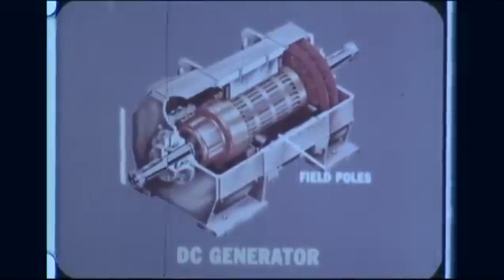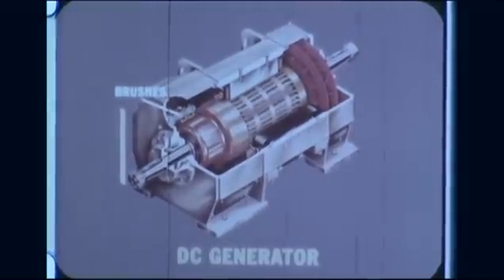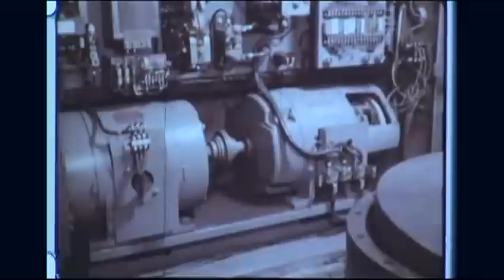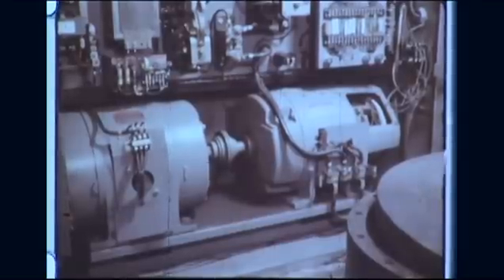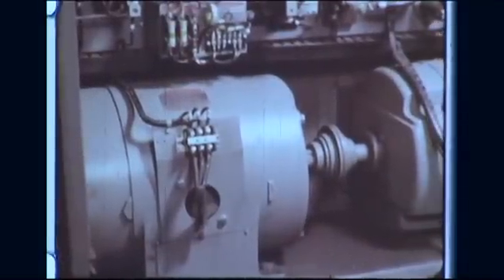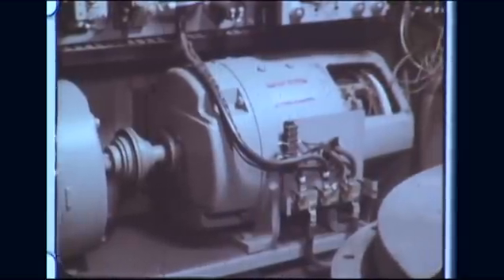In the direct current generator, the field poles, which establish the magnetic field, are stationary. The armature, which contains the commutator, must be the rotating part so that the stationary brushes can collect the current, rectifying it by switching the load current from one set of commutator segments to another. However, the DC generator is limited in capacity because high voltages would cause damaging arcing at the commutator. Therefore, because they are seldom rated as high as 750 volts, they are used only for the generation of power in specialized applications.